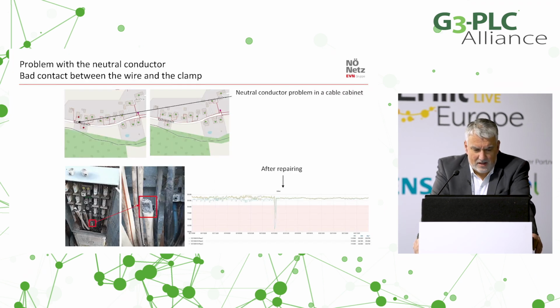There's one other, different example. We had a problem with the neutral conductor, and as you see here, the voltage was like flicker. We went into the field to the cabinet to see what was happening before the customer gets any problems. There was a bad contact between the wire and the clamp, and after we repaired it, you can see on the right side that the voltage level was stable.